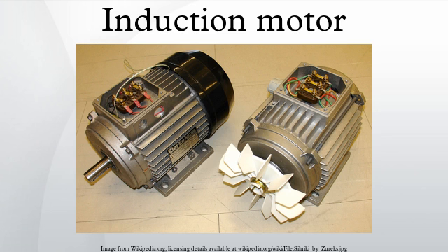Although polyphase motors are inherently self-starting, their starting and pull-up torque design limits must be high enough to overcome actual load conditions. In two-pole single-phase motors, the torque goes to zero at 100% slip, so these require alterations to the stator such as shaded poles to provide starting torque.